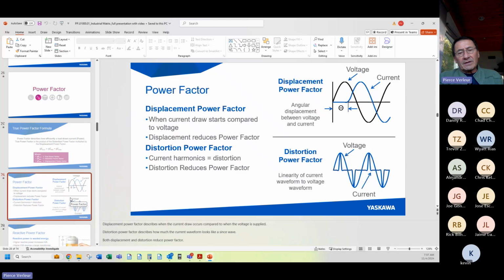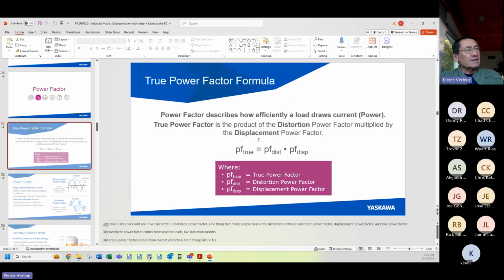If you want your true power factor to be 0.98, you can't have this, which is not a problem with variable frequency drives, and you better fix this. And that's what active front end and matrix technology does. That's why people are using it today. Because the power company is sick and tired of people abusing the power factor and running true power factors in their plants at less than 0.9, 0.85, which is very common. And the grid can't stand it anymore, because the grid's already overloaded.